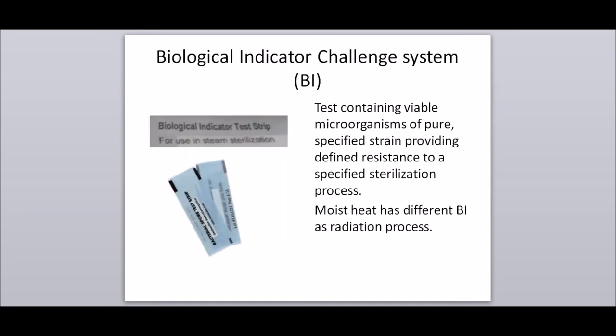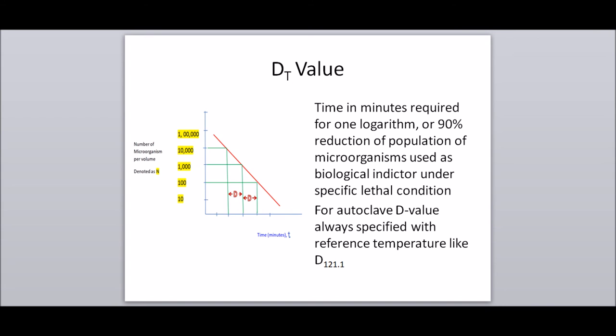Biological indicator challenge system, or BI: a test containing viable microorganisms of a pure, specified strain providing a defined resistance to a specified sterilization process. Moist heat has a different BI than a radiation process. D value: the time in minutes required for one log reduction, or 90% reduction, of a population of microorganisms used as a biological indicator under specific lethal conditions. For autoclave, the D value is always specified with a reference temperature, like D 121.1°C.